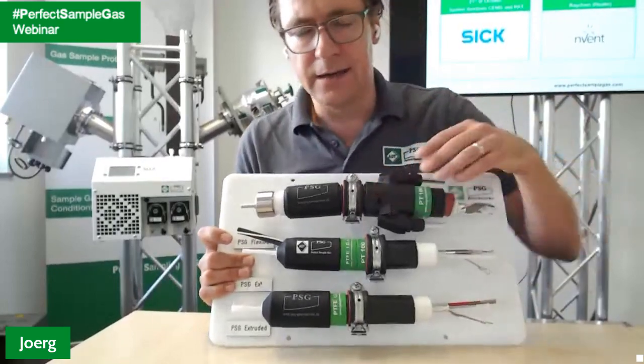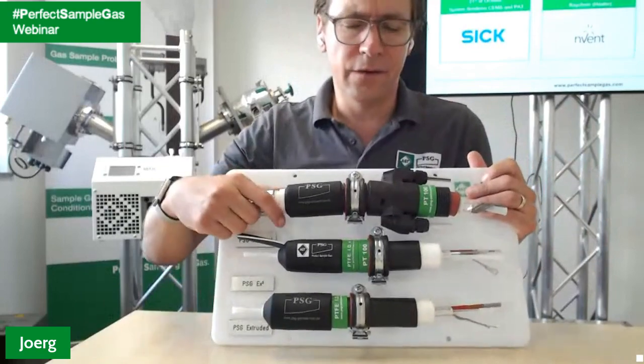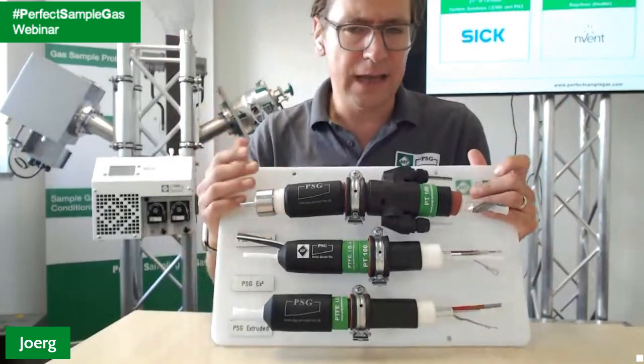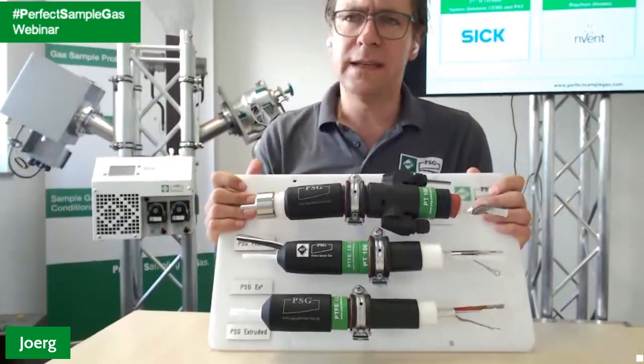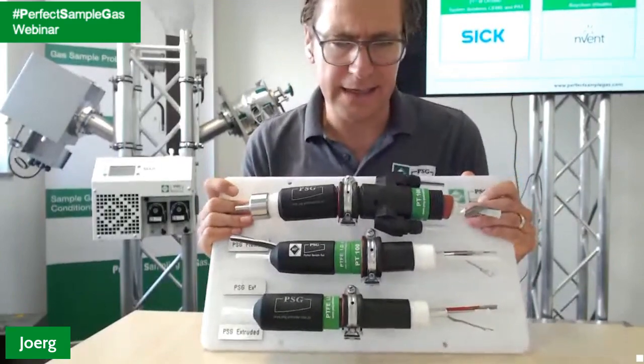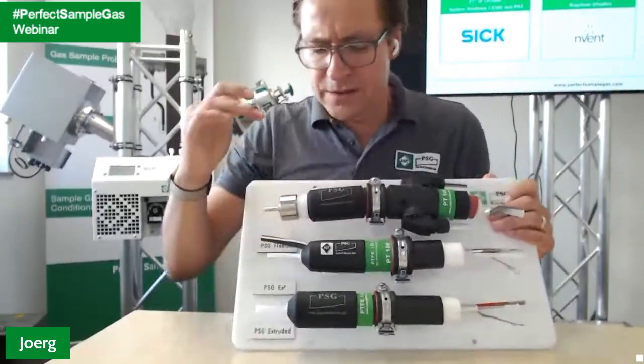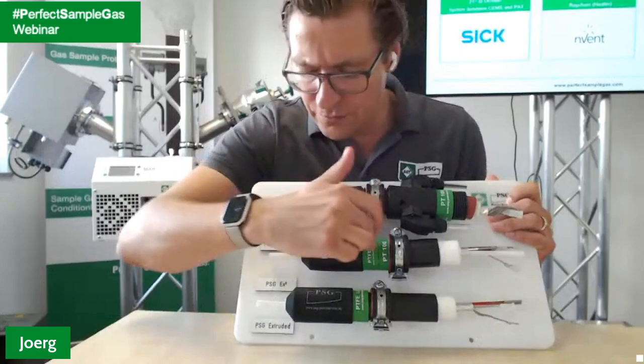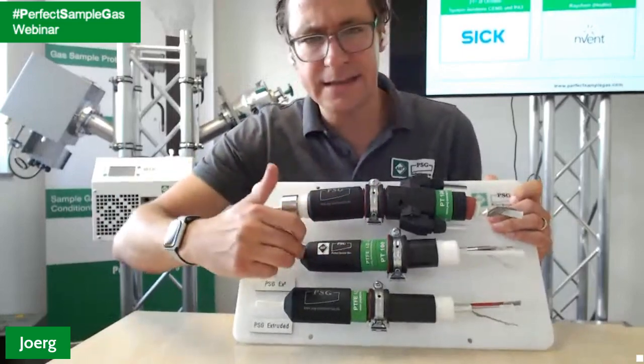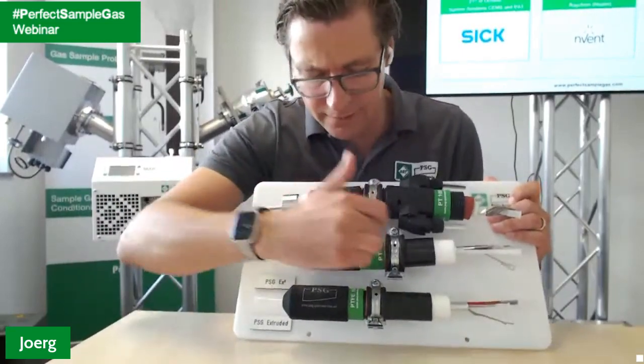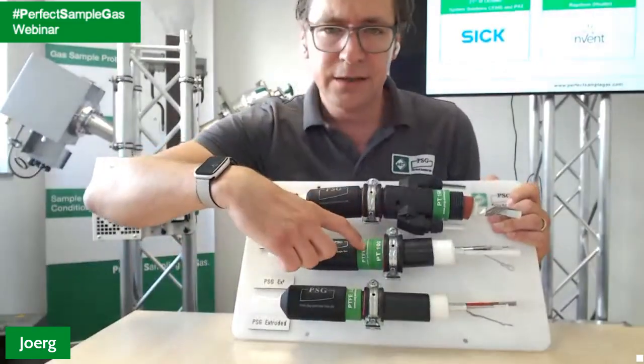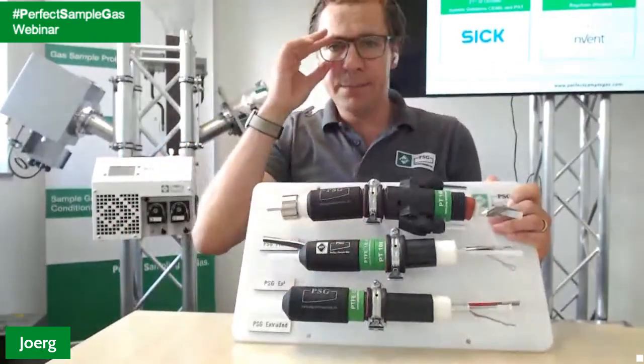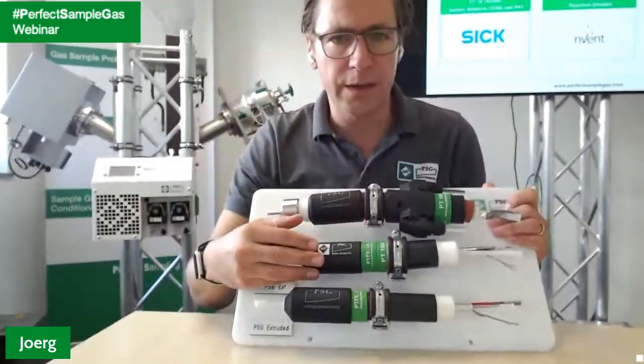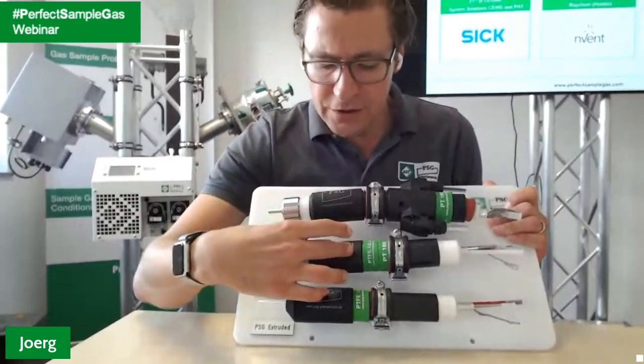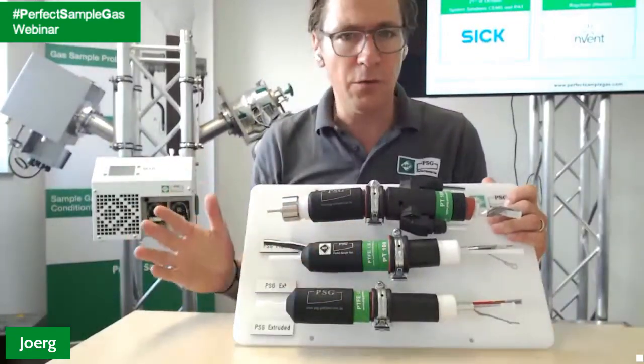The details here, for clogging and other reasons, the main task of the heated sample line will be avoiding condensation. So you have to make sure that your heater really ends here, not here, not here, not here, because then you have a cold spot, and depending on the environment where you do the measuring, a small cold spot can already be enough.